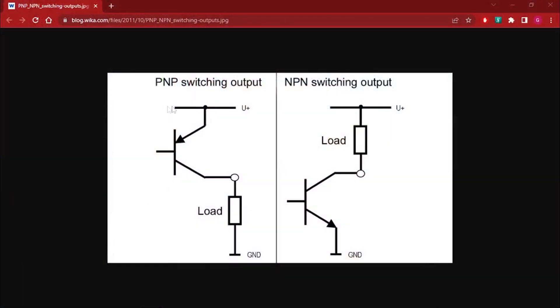Here's a really easy way to remember this if your brain is getting confused. For PNP and NPN, the middle letter is your reference — just remember that. It's not exactly what they stand for, but it's easy to remember: just think negative and positive. The middle letter is my reference. So in PNP, negative is my reference, and with my other lead I'm checking the signal. In NPN, positive is my reference, and with my other lead I'm checking the signal.